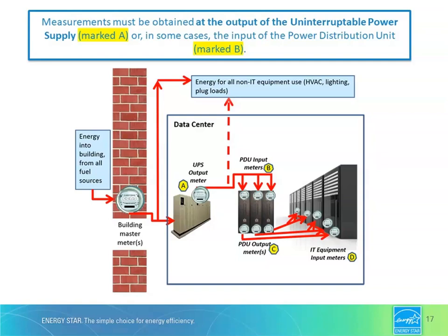So if you're planning to seek certification for your data center or for your building that contains a data center, be sure to meter your IT energy at the UPS output or in some cases at the PDU input. So we'll go over the specifics of those options now.